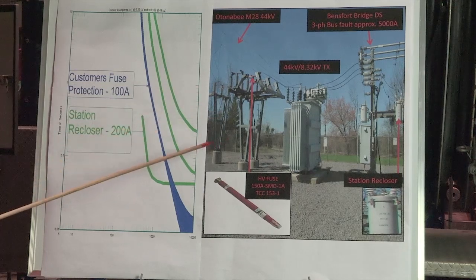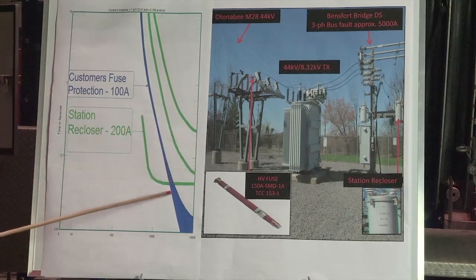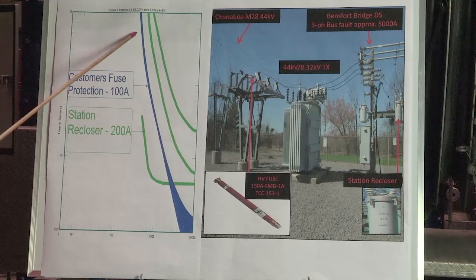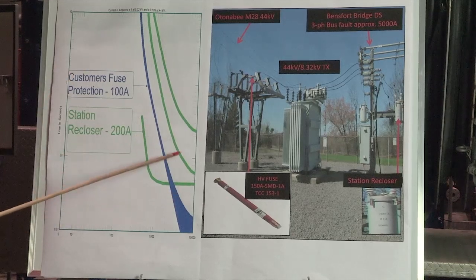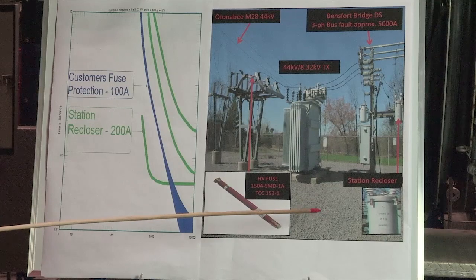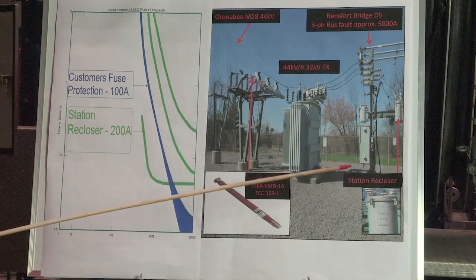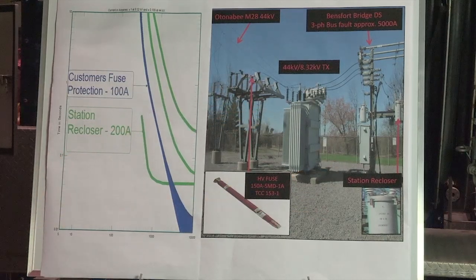Hopefully the fault is gone. If it's not gone, the customer's fuse will take the fault out, and the recloser will not trip, and it'll be just those 10 customers or 15 customers out of power, and not the entire F1 or F2 feeder.